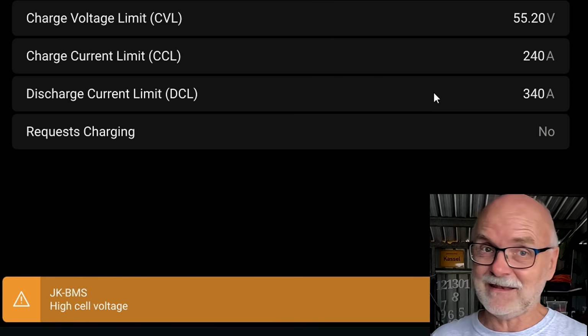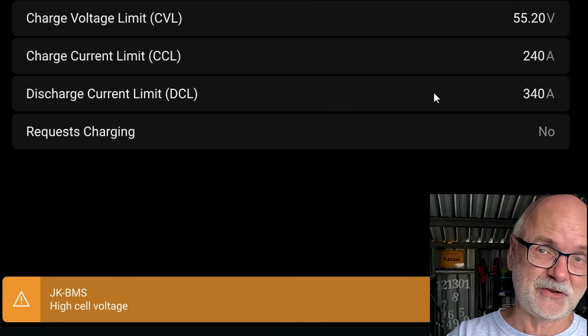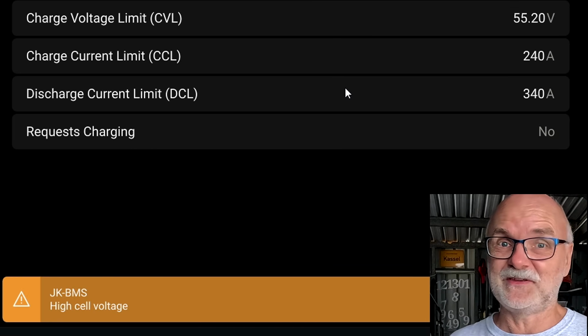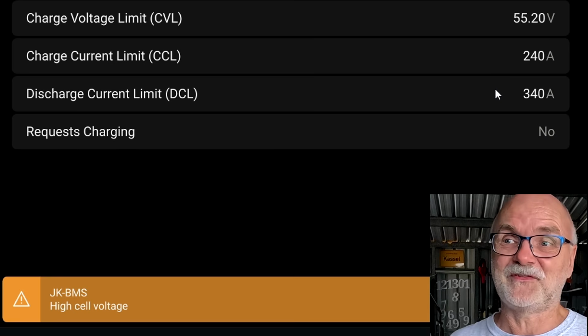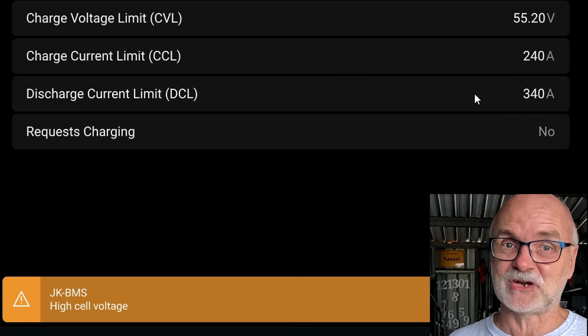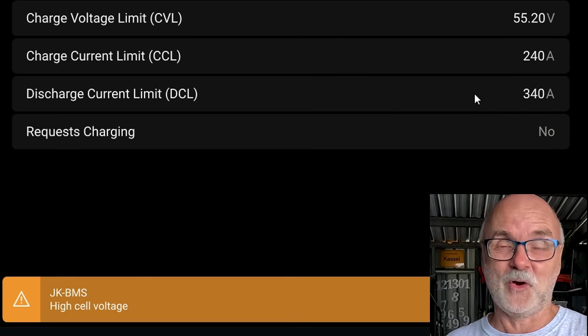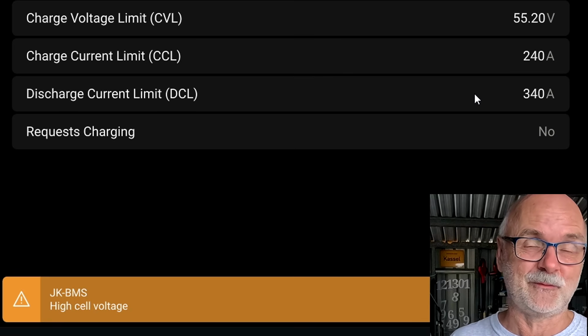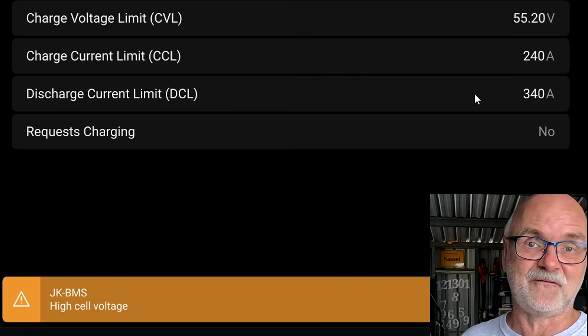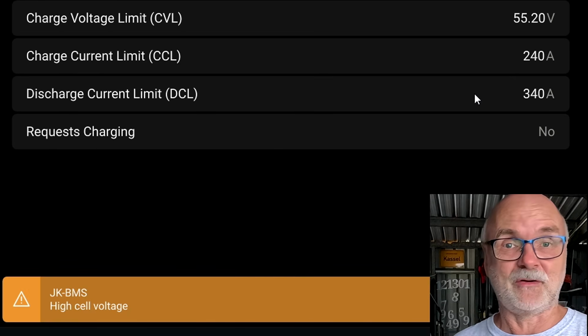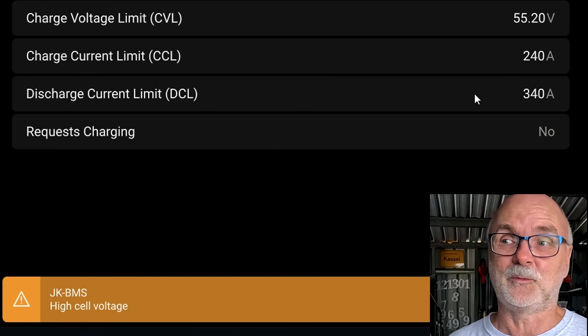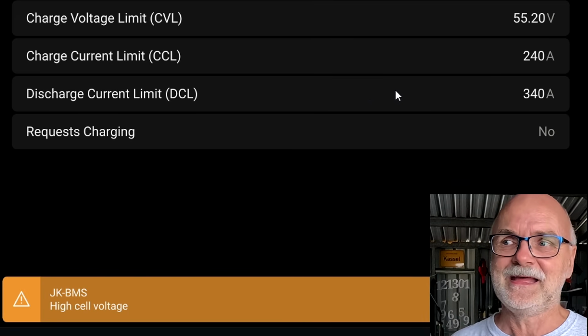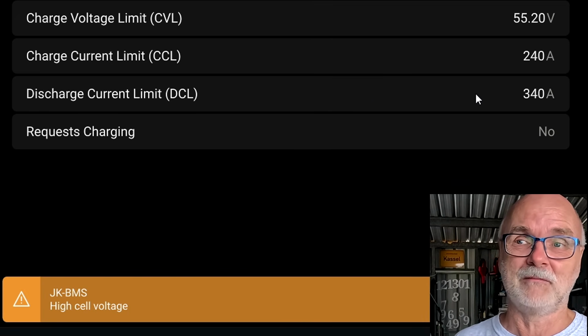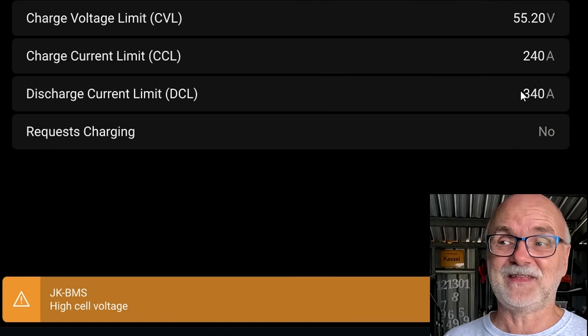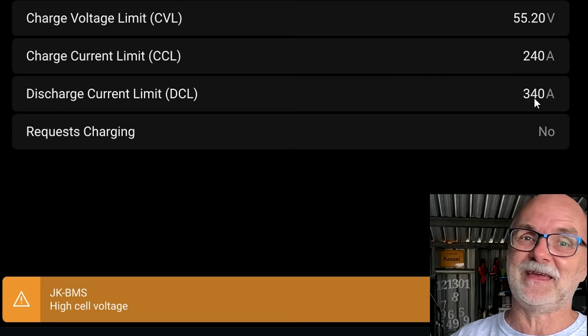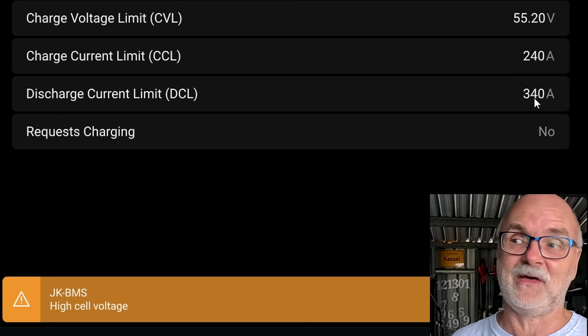If we would have an under voltage protection, a cell low voltage alarm, this would then mean we cannot discharge our battery any further, and we would see a reduction in requested discharge current for your inverter. That means your inverter takes less energy from your batteries and more energy from the grid if necessary. If you are off-grid and don't have a grid as a second energy source, it will ignore the DCL altogether as long as the DCL is over 0 amps basically. As long as there's 1 amp requested, it takes whatever it can from the batteries because there's no other energy source.